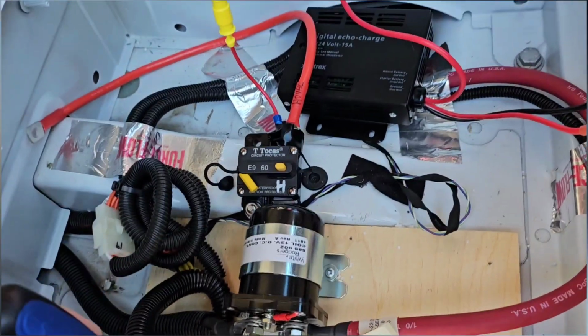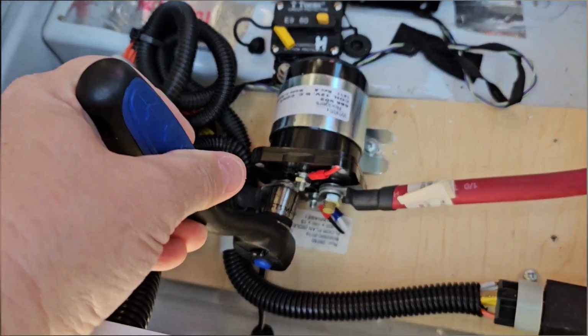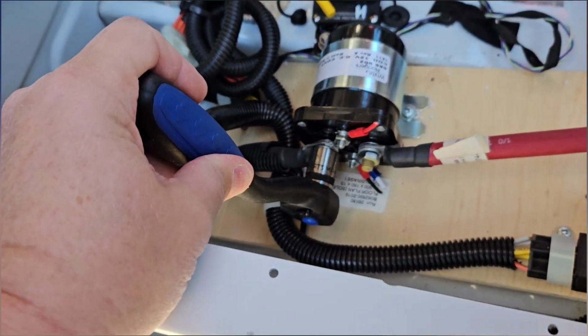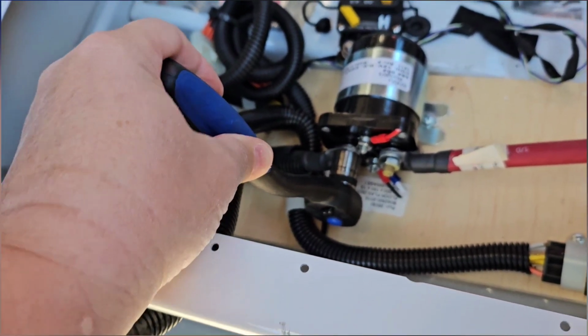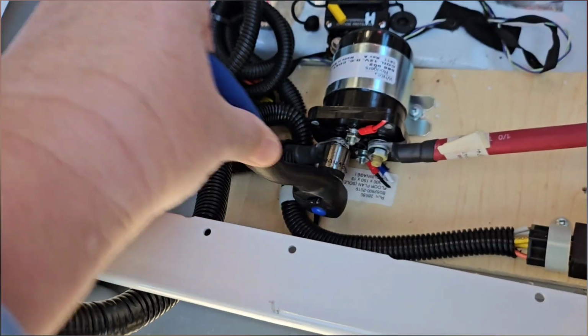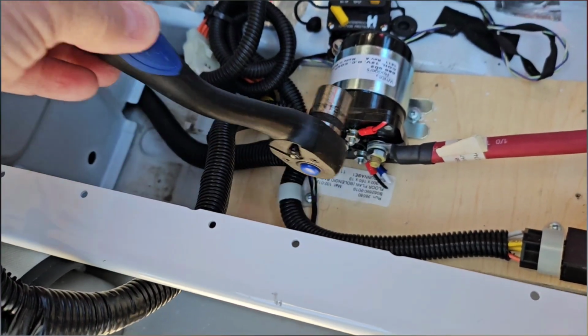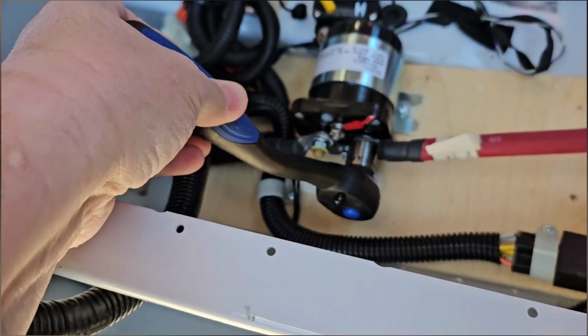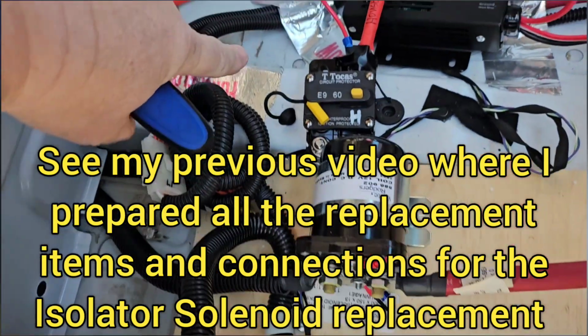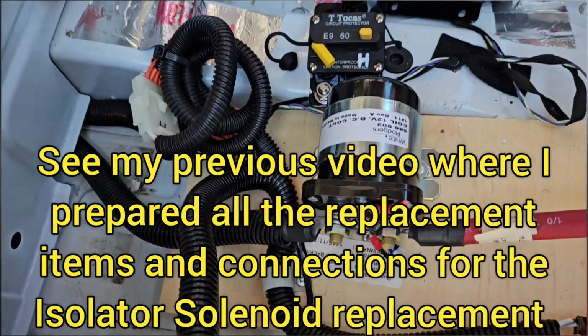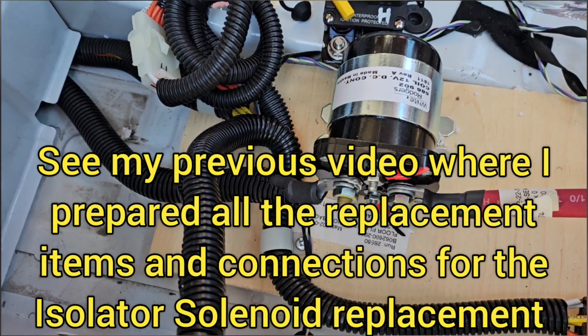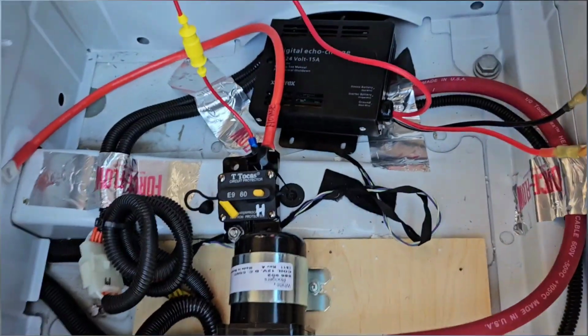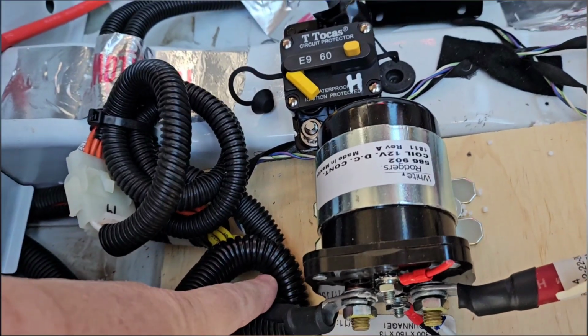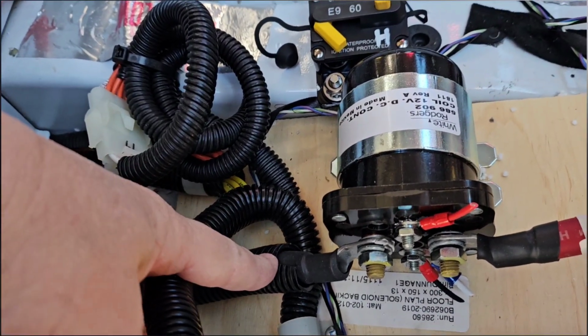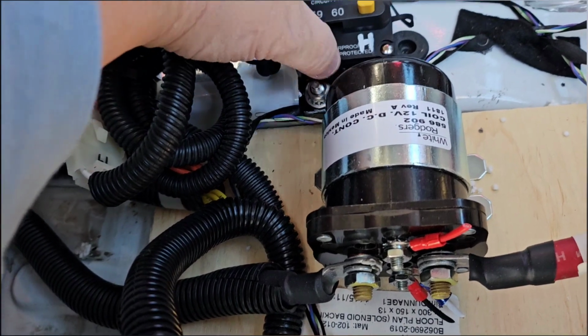Okay, I have a 13 millimeter socket and an insulated ratchet wrench. Like I said, I'm going to treat these as hot, so I'm going to loosen both of these. I have my house battery circuit breaker ready, so when I remove this house battery cable from the isolator solenoid, I'm going to be immediately putting it on this connector on my 60 amp house circuit breaker.